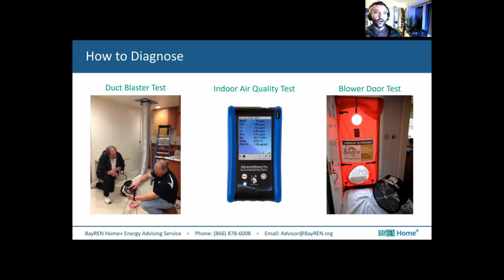They do the math and they say all the leakage, all the gaps, and everything in your house, if we combine that all, you're looking at 144 square inches, or 1 by 1 foot. And that's pretty typical. The woman's house I spoke about today, her energy audit was 77 square inches. So maybe 8 by 8 or 8 by 7 or so is this hole. If you take all that accumulated holes through your outlets, around your windows and doors, through those top plates, bypass leakages through electrical, plumbing, through your floor, ventilation, take all that gappage, combine it. That's your goal. You've got this square now, and your goal is to make it smaller, right? And the more you tighten it, the more control you have over retaining energy and sustaining temperature.